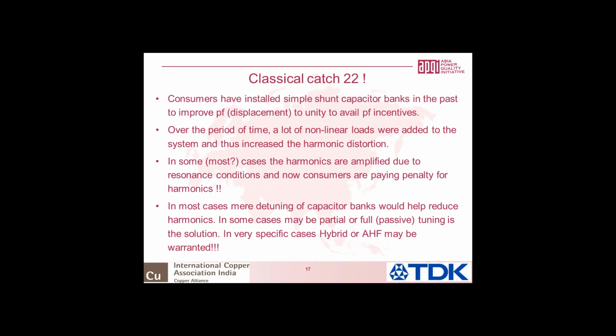So in most cases, the harmonics are getting amplified due to a resonance condition, which fortunately could be a local resonance within the network and not a global resonance. Otherwise, you can even have a serious cascaded tripping in the power system. And because of this harmonic increase, depending on the state, you're paying a penalty for harmonics.